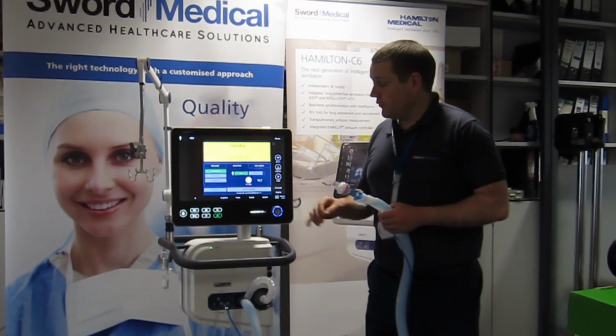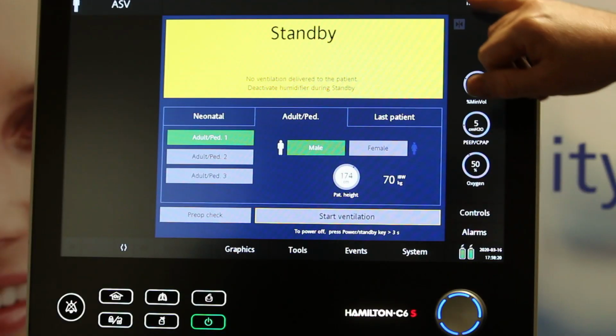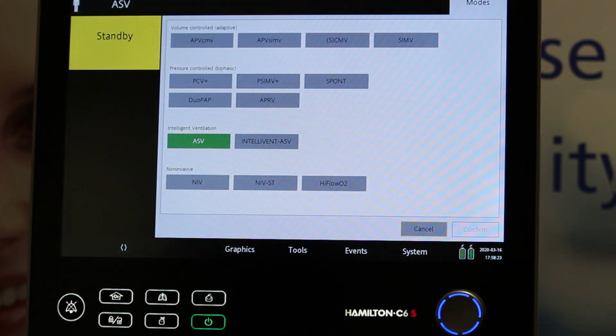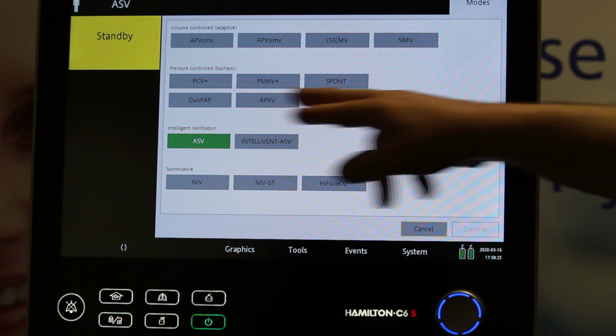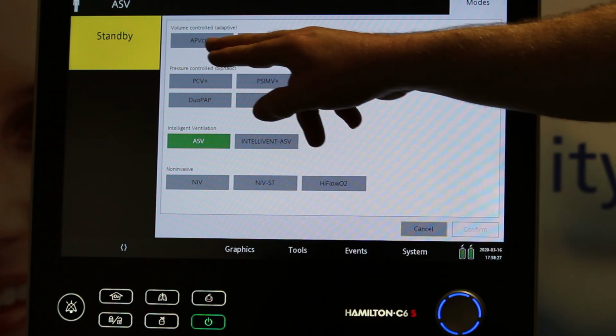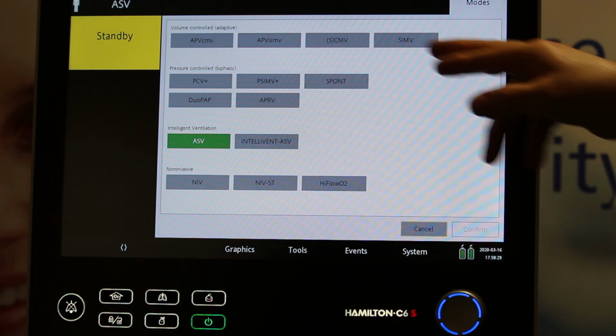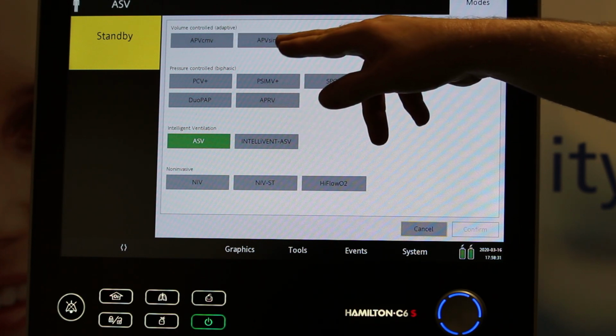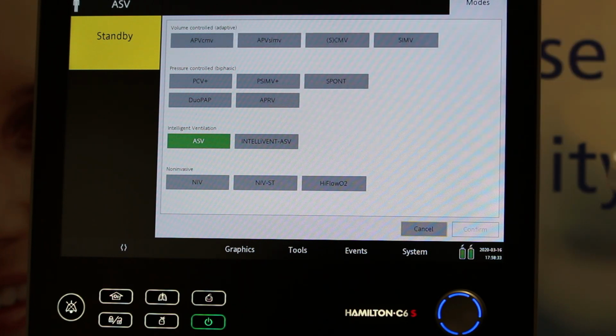So before I put on my lung and run it, we're going to have a look at the modes. If you see in the top right hand corner, we have the modes button, and here are all of the modes that are on the ventilator. So we have 4 volume controlled modes. We have APV CMV and APV SIMV. APV stands for adaptive pressure ventilation, CMV stands for controlled mechanical ventilation, and SIMV stands for synchronized intermittent mandatory ventilation.